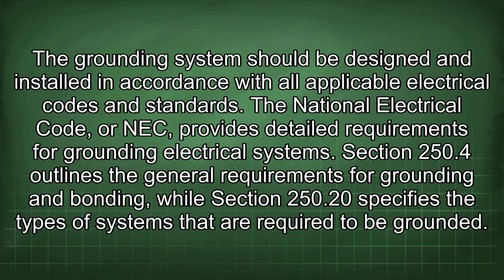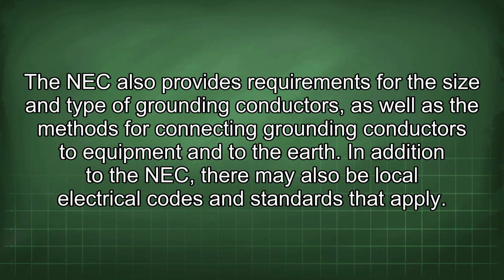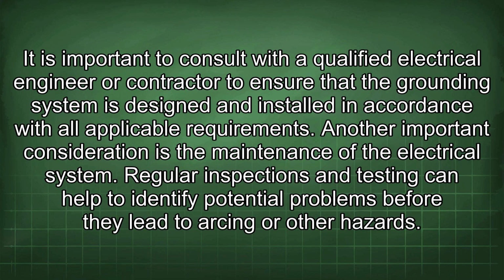The grounding system should be designed and installed in accordance with all applicable electrical codes and standards. The National Electrical Code, or NEC, provides detailed requirements for grounding electrical systems. Section 250.4 outlines the general requirements for grounding and bonding, while Section 250.20 specifies the types of systems that are required to be grounded. The NEC also provides requirements for the size and type of grounding conductors, as well as the methods for connecting grounding conductors to equipment and to the earth. In addition to the NEC, there may also be local electrical codes and standards that apply. It is important to consult with a qualified electrical engineer or contractor to ensure that the grounding system is designed and installed in accordance with all applicable requirements.